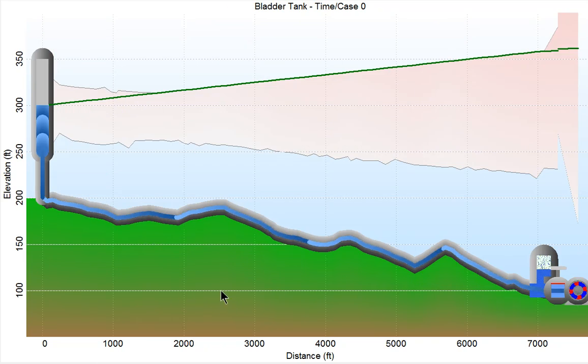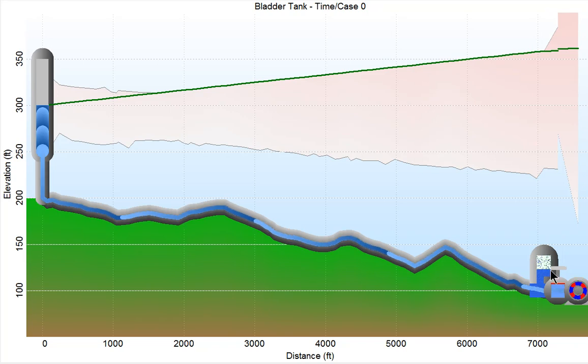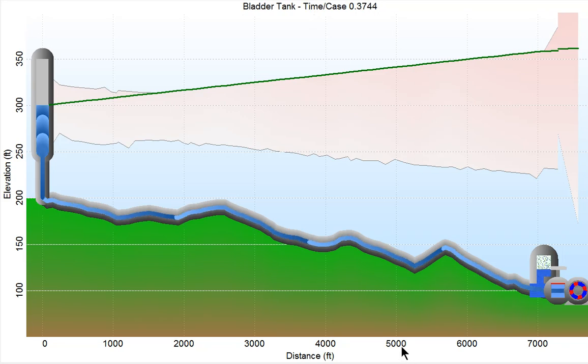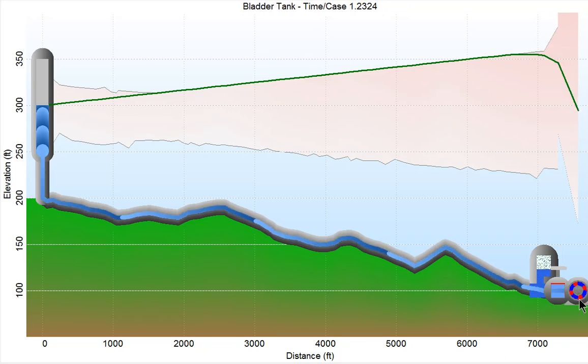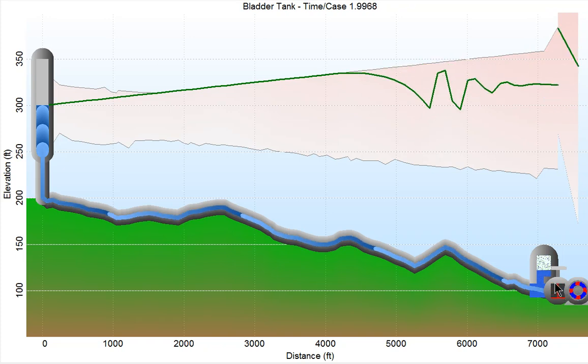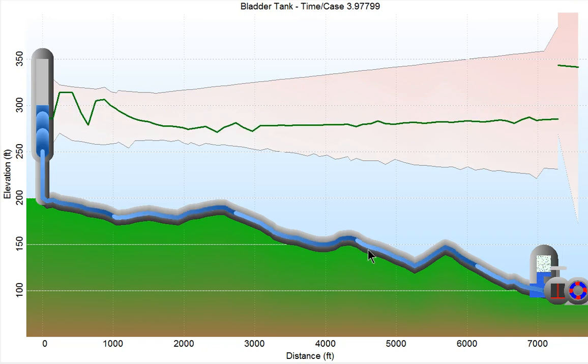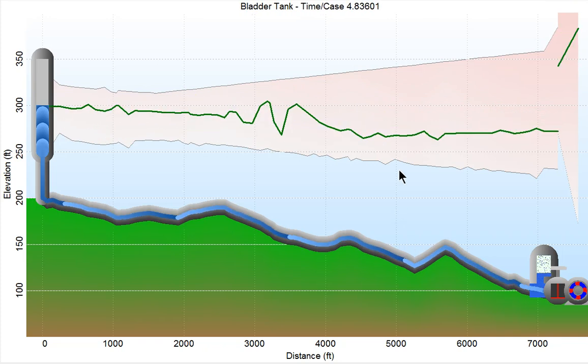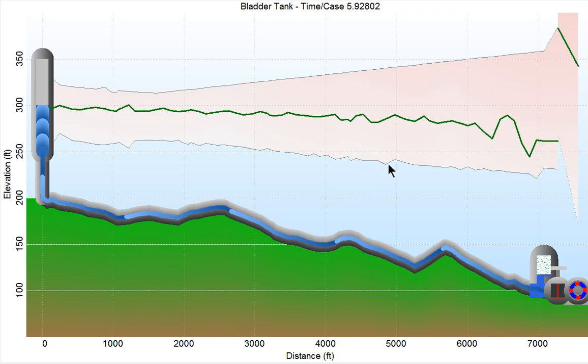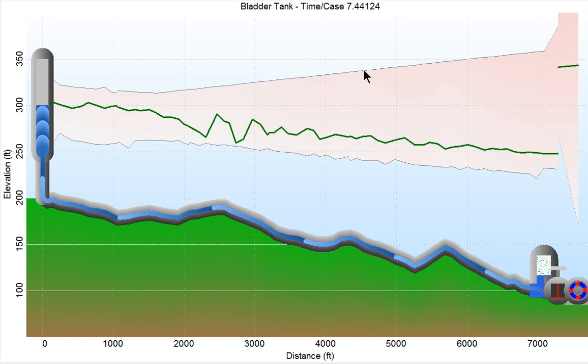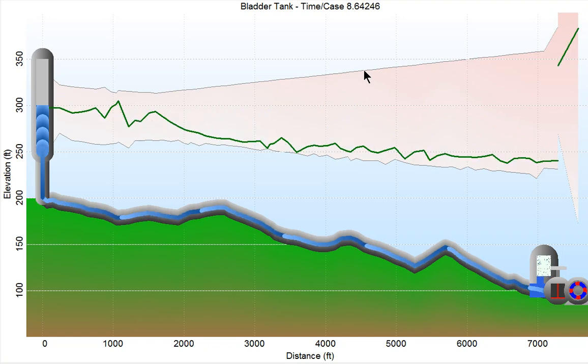The final analysis I want to show you is with a surge tank. The surge tank will, when the pressure drops, start providing water to the system. The pump slows down again, the check valve closes, but now water continues to flow to the tank and the pressure doesn't drop below this line. The maximum pressure barely goes above the steady state pressure line.